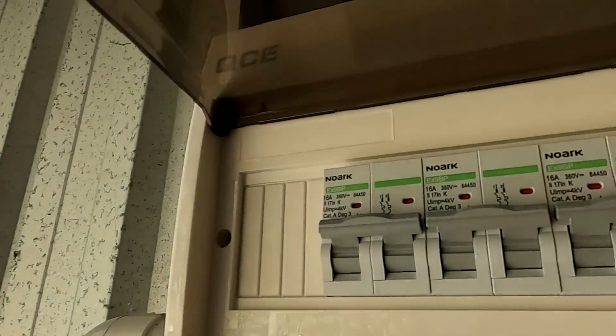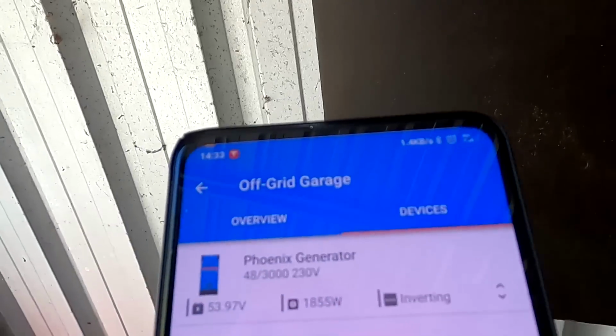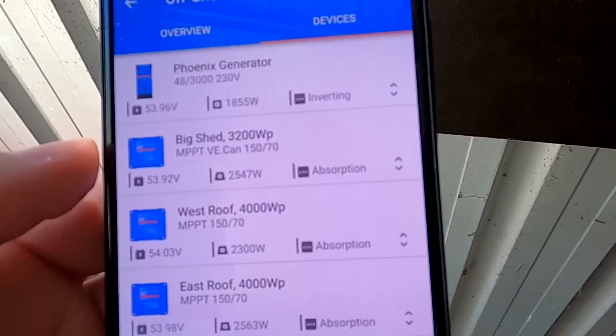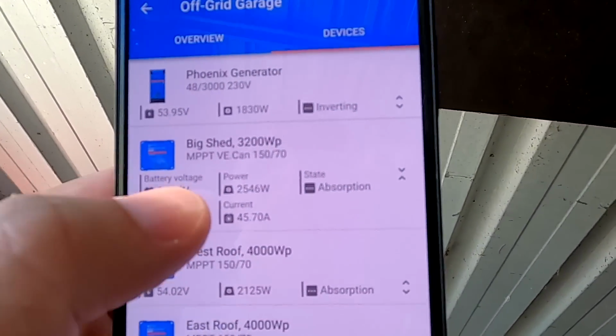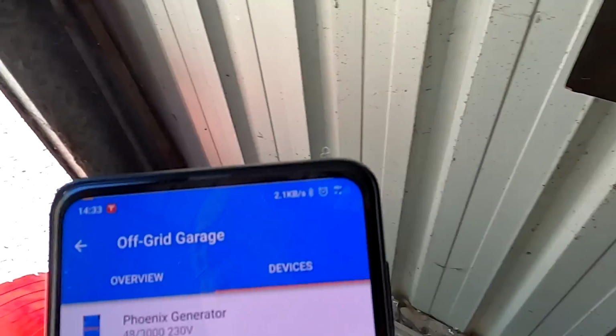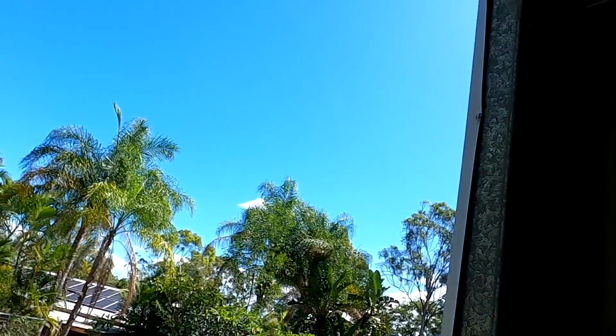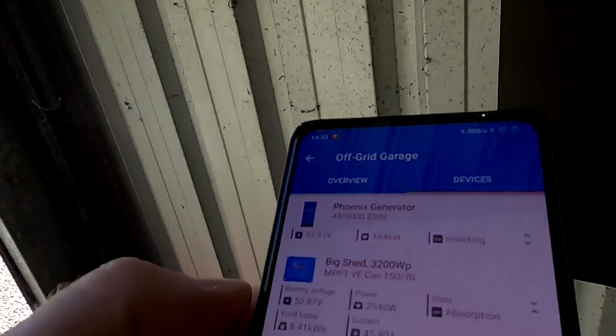And this is a 3.2 kilowatt system, 8 Hyundai shingled panels, 400 watts each, 2 of them in series and then 4 strings in parallel. There are the 4 strings. But I think we should produce a bit more than only 2.5 kilowatts now, right? We've got the optimal conditions, no cloud, nothing, pure sunshine.